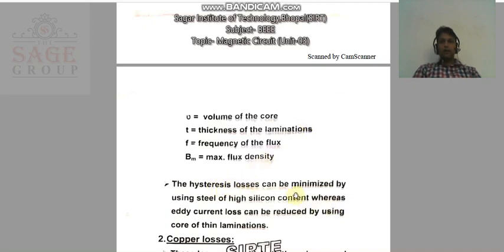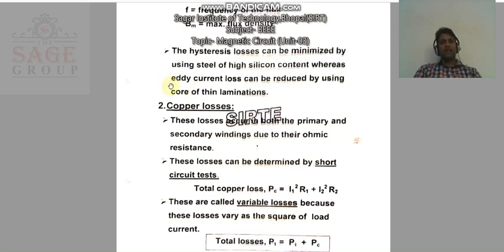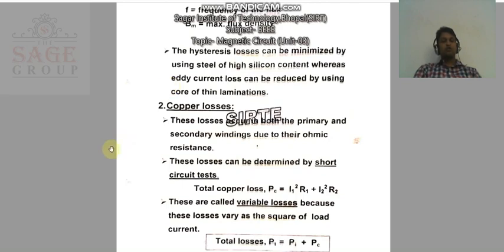Hysteresis loss can be minimized by using steel with high silicon content, whereas eddy current loss can be reduced by using a core made of thin laminations. We know that the core is made of thin plates combined together, but each plate is insulated from the others. By using these two methods, we can reduce the core loss of the transformer.